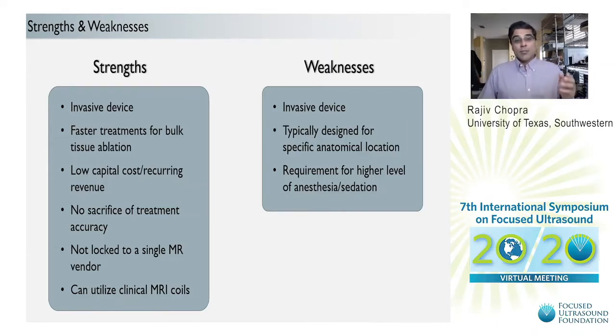And maybe one of the most important strengths, which is not obvious, and in fact was not even obvious to us until we started using them, is that they can be integrated directly into clinical MRI coils in many cases, again, if designed properly. The importance of that is that physicians using the procedure are seeing the exact same image quality they're used to diagnostically. We're not asking them to take a decade step back into images with a body coil or substandard coil imaging. In the case of the prostate technology I described, they're using 32-channel coils with SENSE, fully accelerated imaging, with the spatial resolution they want. And so the perception is that you're integrating something new into what they already do, rather than having to sacrifice to get access to it.